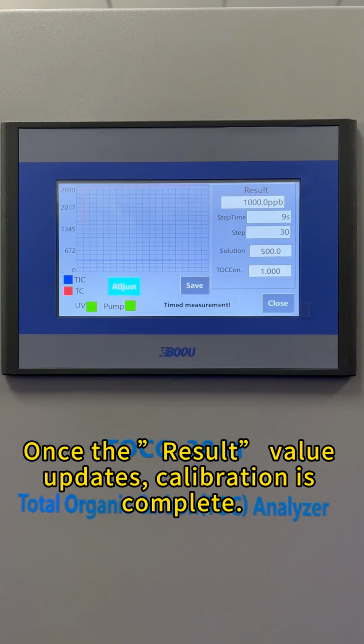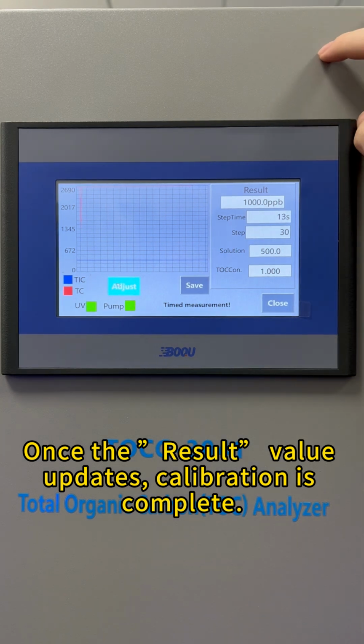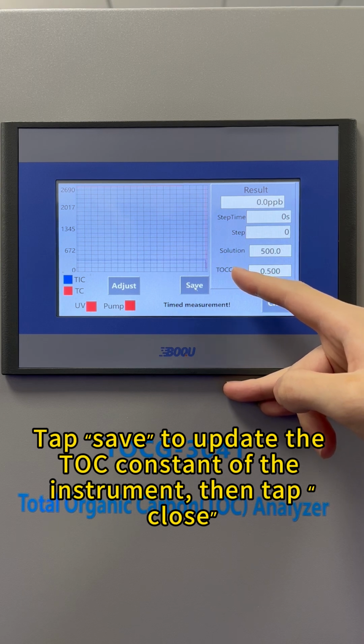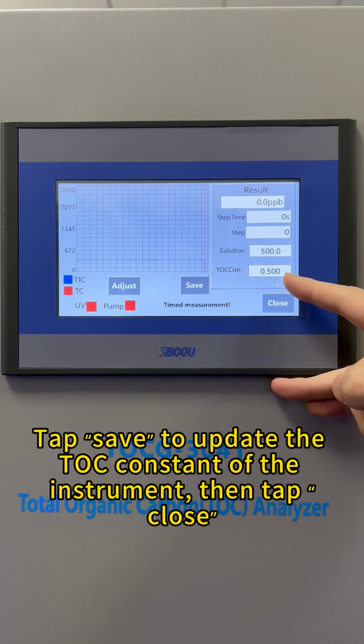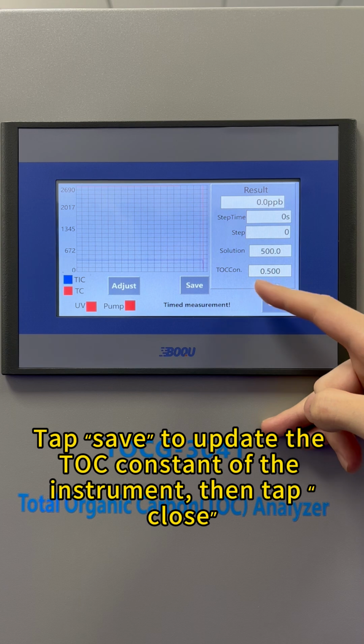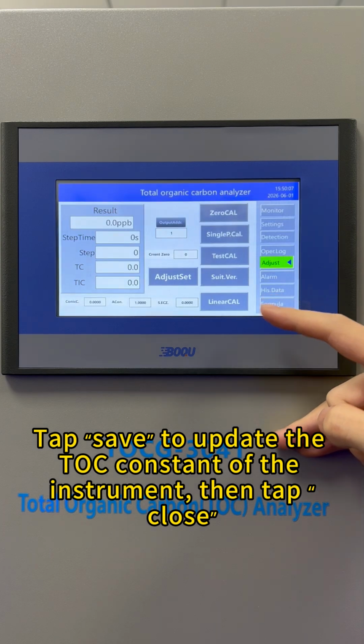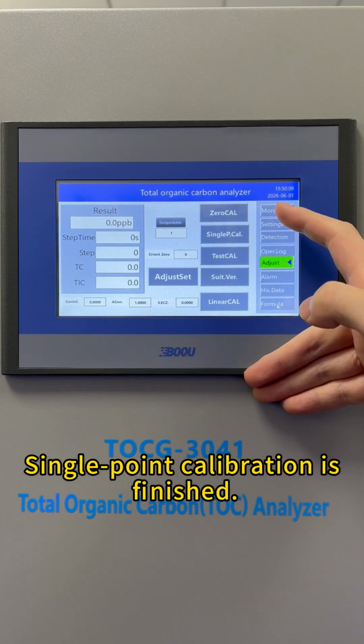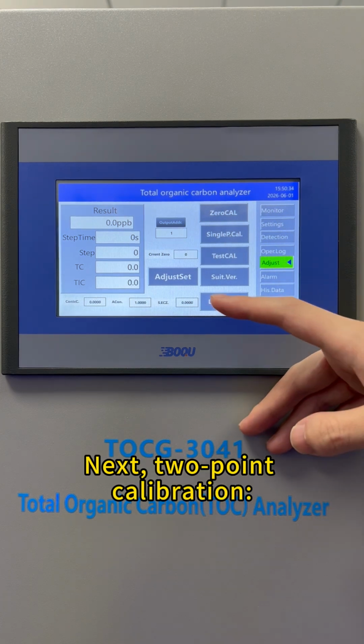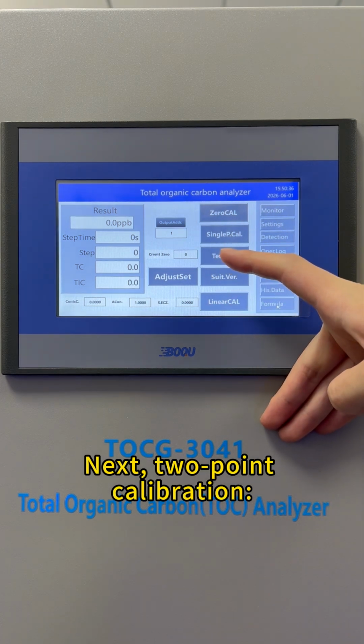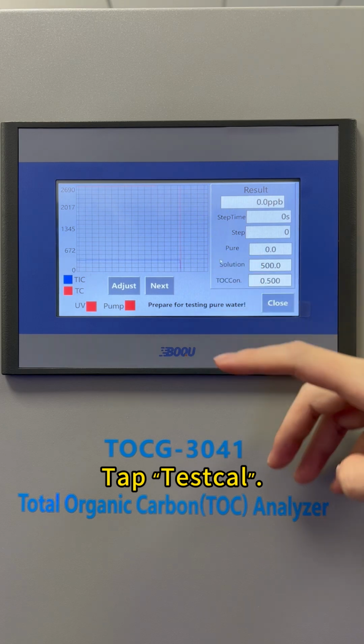Once the result value updates, calibration is complete. Tap Save to update the TOC constant of the instrument, then tap Close. Single point calibration is finished. Next, 2-point calibration. Tap Test Cal.